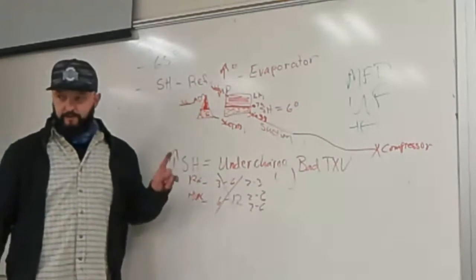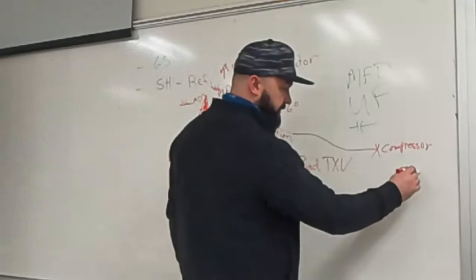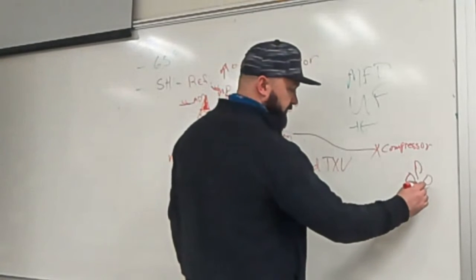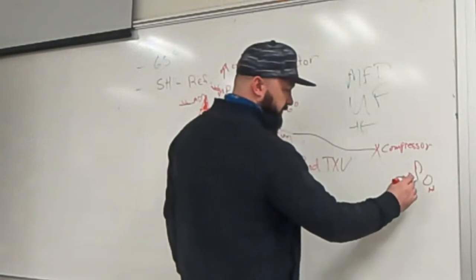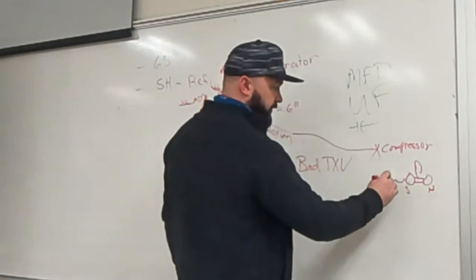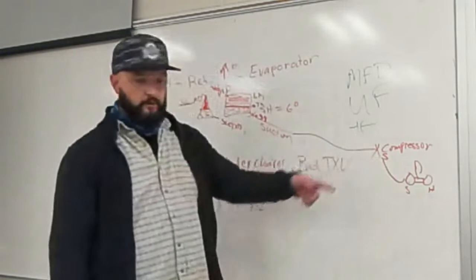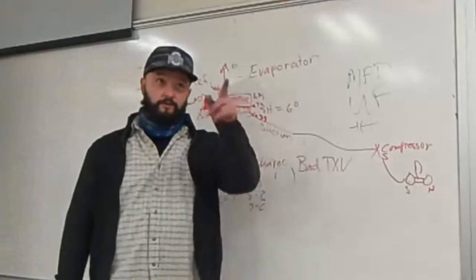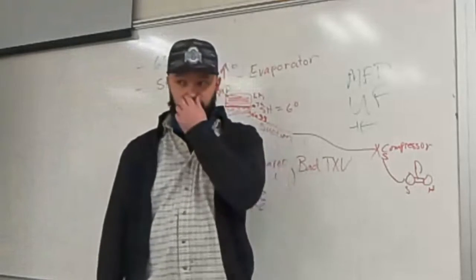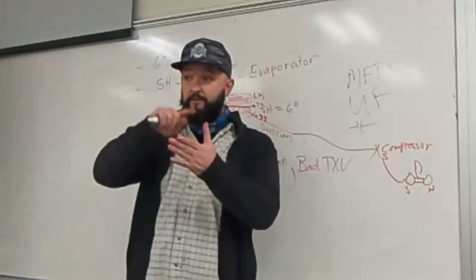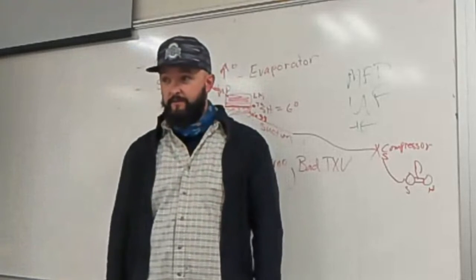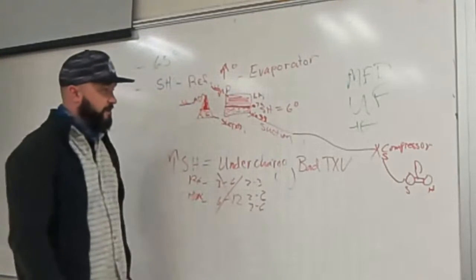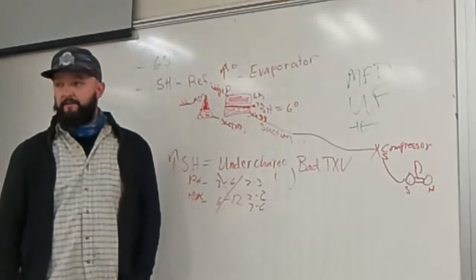Before I erase this — you've got your manifold here with your suction gauge and your head pressure gauge. When you hook up to your suction line you're going to read a pressure. You're going to convert that pressure using a PT chart to a saturation temperature. The gauge will tell you what that temperature is — that's telling you the saturation temperature in your coil when the refrigerant starts changing to a gas.